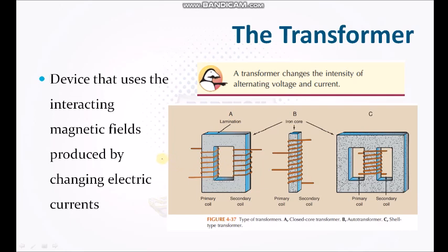So electricity from the main source, for example from the electric companies, comes into the department, towards the transformer of the X-ray tube. This is the primary side, the primary coil. Electricity will only be provided to this coil.